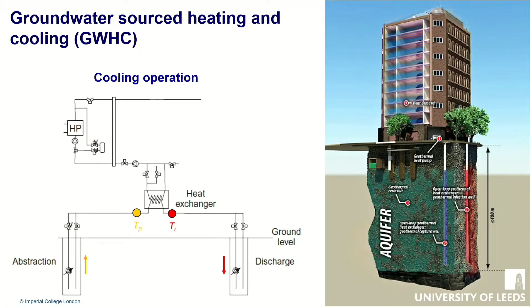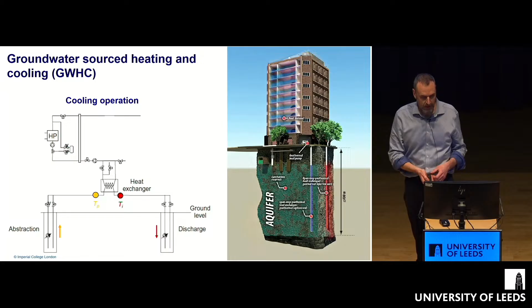If we want to provide cooling, we can switch this around. We take out our groundwater, which remains at a fairly constant temperature—typically 13, 14, 15 degrees—and still pass it through the heat exchanger, but now use the heat pump to drop the temperature and provide cooling, injecting some waste heat back into the aquifer. This is often more efficient than using air source heat pumps, because of the relatively constant temperature of the groundwater.